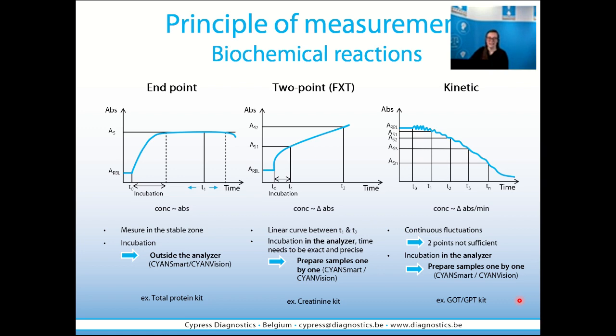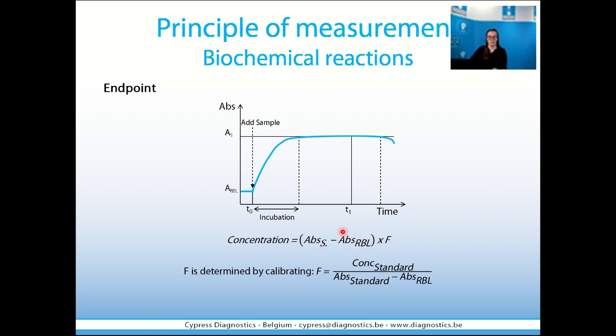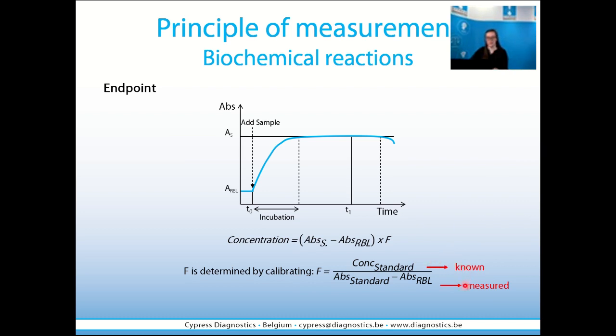You don't need to memorize these charts by heart. We will see them in more detail and explain which implications are important. In the calculation of analytes, we get the concentration by measuring the absorbance of samples. We deduct the absorbance of the reagent blank and we multiply it with a factor. This factor is determined by doing a calibration. The calibration uses parameters which are known and parameters which are measured. The software has these calculations integrated.